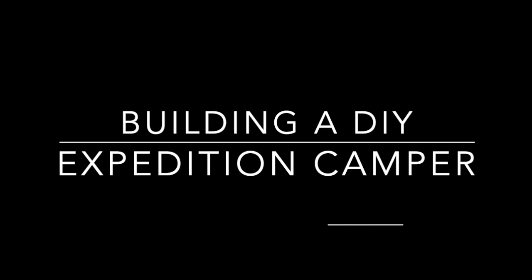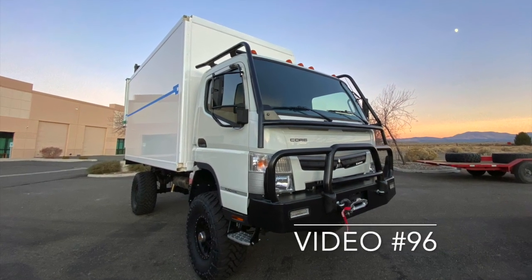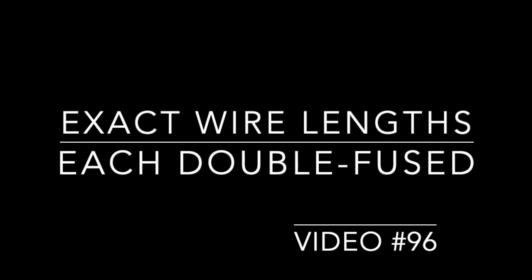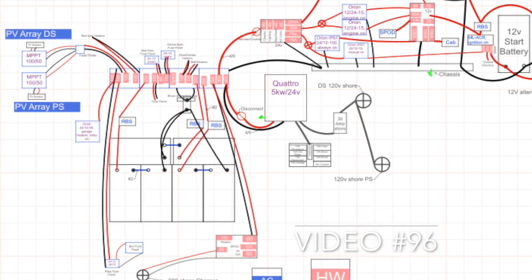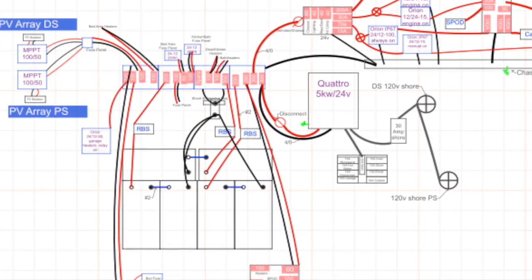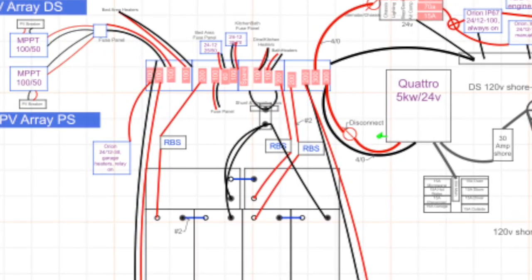This may be the largest camper electrical system that I know of, at least in battery capacity. This all started as a complete DIY expedition camper all the way from the chassis up. We've got six 300 amp hour lithium iron phosphate batteries. We have three different shore connections at two different voltages, multiple solar systems, dual alternators — both 12 and 24 volt — remote battery switches to disconnect every single one of these battery pairs, and so much more in this thousand amp distribution system.